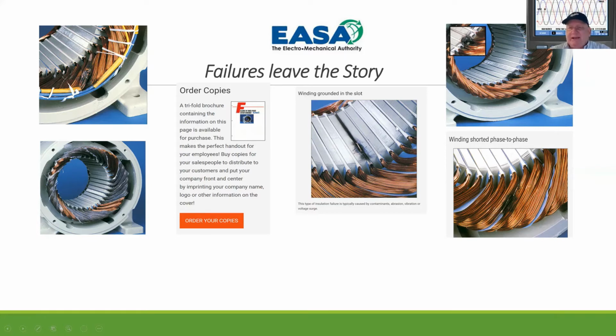This one happens to be, as you can see, the inner core, and there could have been dirt or scraping or bearing failure that scrubbed, and so it ended up creating heat, burnt the slot insulation, and ended up shorting the winding there. This shows a phase-to-phase failure, meaning that there was a breakdown in the insulation between phase A and phase B, or it could have been C and A, whatever. But you'll see that there was actually a short. So this had 480 volts here and 400 volts there, and it actually jumped across. So it could have been high voltage between these two phases that blew that. This happened to be high voltage to ground, and had a failure in the slot insulation itself, so that it ended up shorting to ground. Again, this is available on EASA.com, and you can get this failure document.